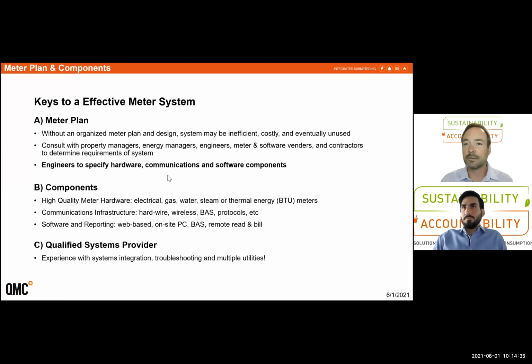We've had lots of systems get put in place where meters were just put in and were needed for billing as an example. They didn't meet that requirement and again had to be pulled out. So that was an example of all the stakeholders not being involved in the decision process. And then we look at these three components: meter hardware itself, communications infrastructure, and reporting systems. And if you don't have all three of those components mapped out before the system is designed, specified, and deployed, it's going to be an incomplete meter system.